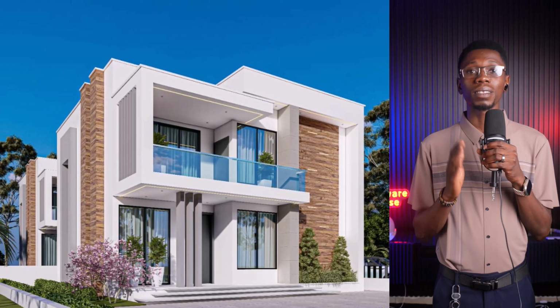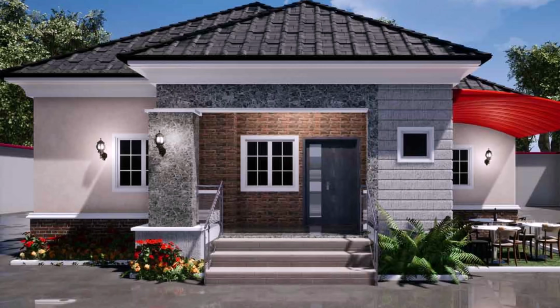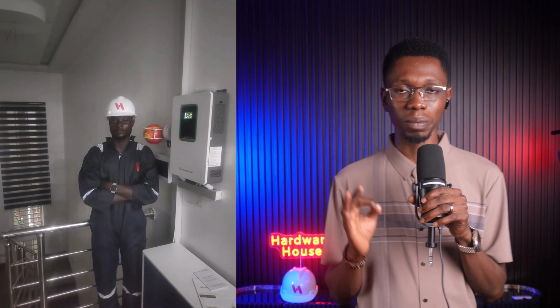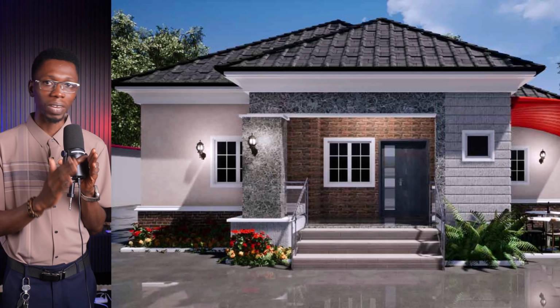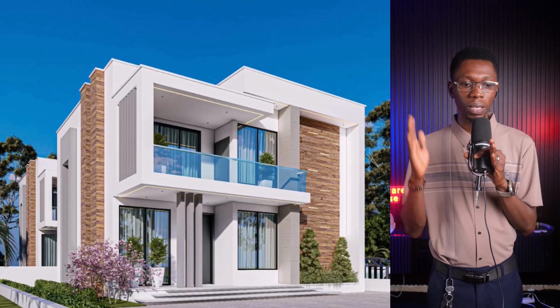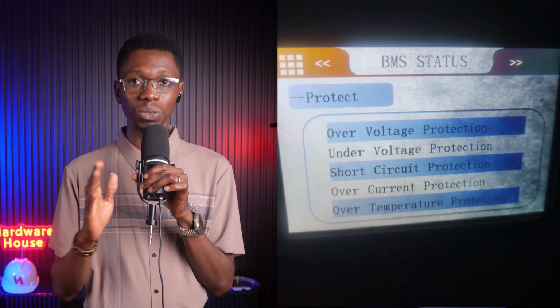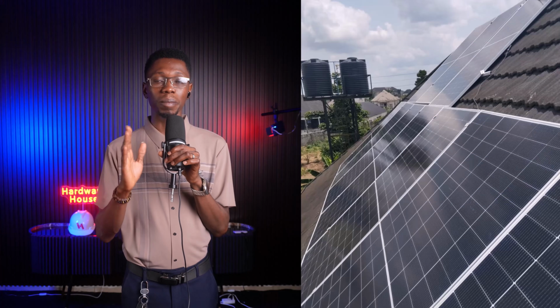So if you own a 3 to 5 bedroom duplex or flat, we just concluded a project on a 5 bedroom duplex apartment for light load. And that would also fit in a 3 bedroom flat or duplex to a 5 bedroom duplex. The budget, the number of panels, the number of batteries, the inverter capacity, all you have to do is just copy and paste. We're also going to be showing you the load calculation that we did and all the safety system that we used to be able to set up this system perfectly well. So let's dive in.